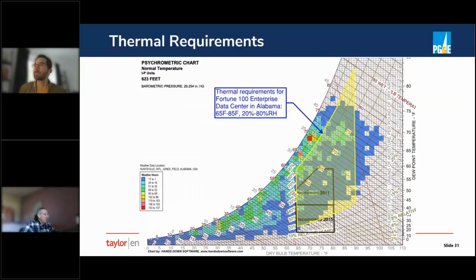This is one that we've been working on or worked on that's in Alabama. And here's the ASHRAE envelope. It has changed over the years, it's gotten wider, but relative to what they're using in this data center, it's still pretty restrictive. This data center is only using an 80% maximum RH, doesn't have a maximum dew point. And what this allows them to do is to avoid any sort of mechanical cooling. All the cooling for this data center is done with an air economizer and direct evaporative cooling, which is pretty impressive in Alabama.